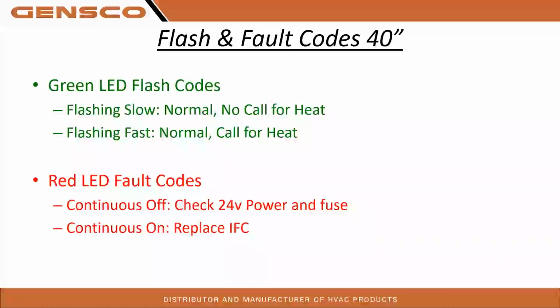Okay. So flash and fault codes on 40-inch furnaces. We've got some green LEDs and some red LEDs. Depending on the model of the 40-inch furnace, we'd have a green CFM light as well. I didn't throw that in there, but let's talk about it real quick. That green CFM light is communicated from the motor module, the motor itself, to the control board, and it is one flash per 100 CFM generated from the motor. So it's not the board telling the motor 6 flashes, 600 CFM. It's the motor saying, I'm making 600 CFM, put 6 green flashes on that light.